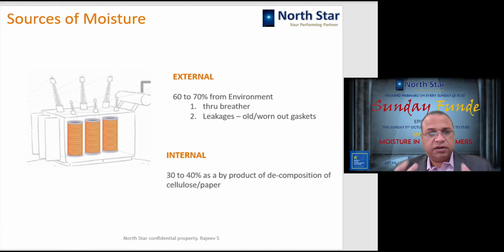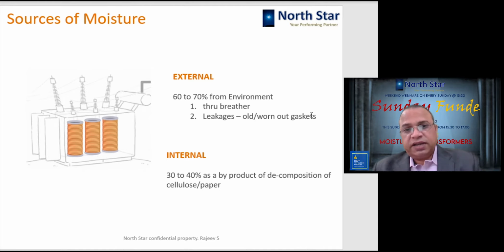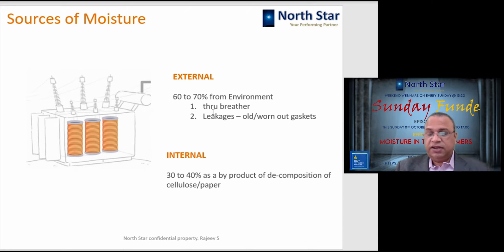Another avenue of external moisture going inside is leakages. Old or worn-out gaskets, especially those put in a non-oil area, meaning the conservator space where there is no oil, are more susceptible to leakage, as are any other gaskets in the transformer which are not supported by the oil inside. Okay, so such gaskets are likely to absorb moisture when the transformer is in a cooling-off period. So this also causes moisture ingress inside the transformer. So what does that mean? That leakages are not to be taken lightly. They affect the transformer insulation quality, though apparently it doesn't seem like that.